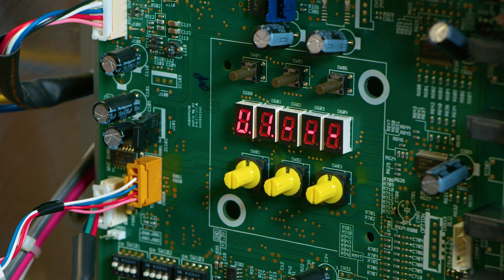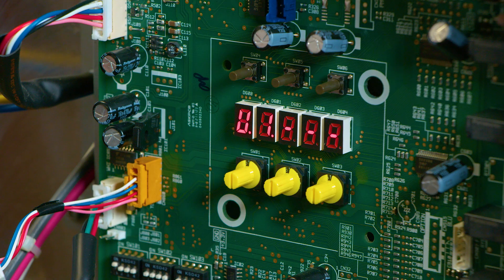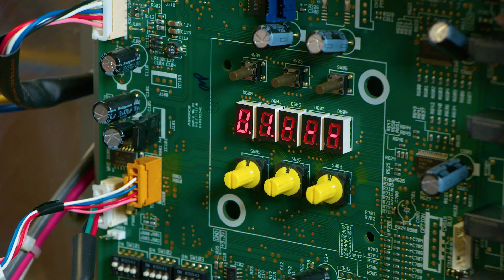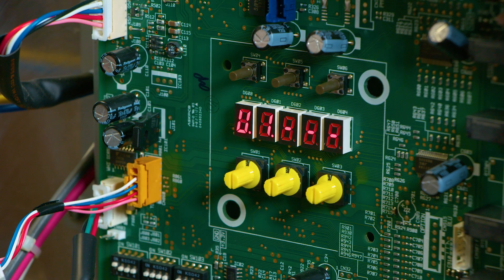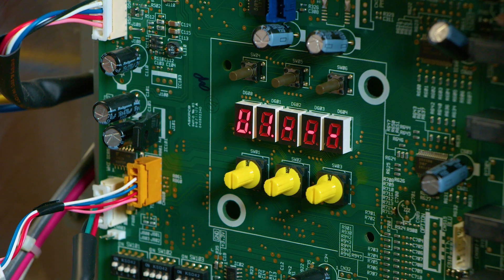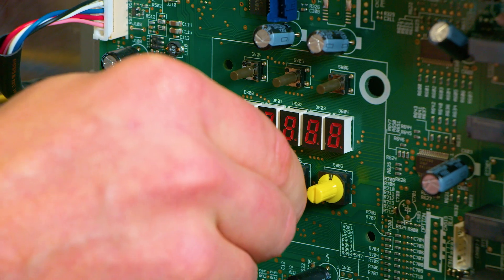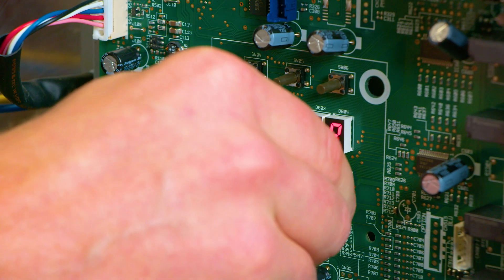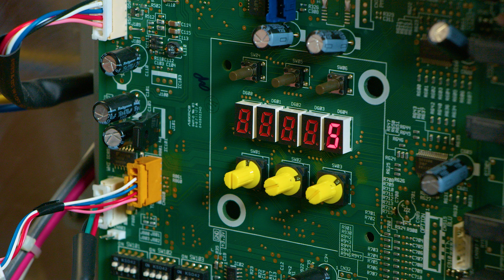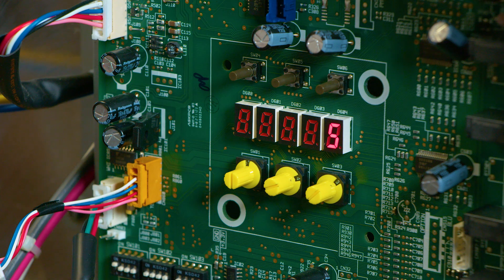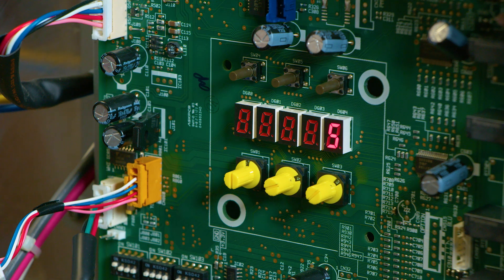If the auto addressing process has been successful, the system will display U1 dash-dash-dash. To check how many units have been connected, you can place the dials to 1-4-3. The quantity of indoor units will be displayed on the right hand side.